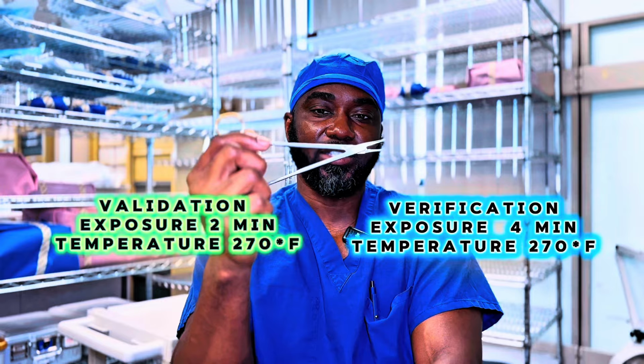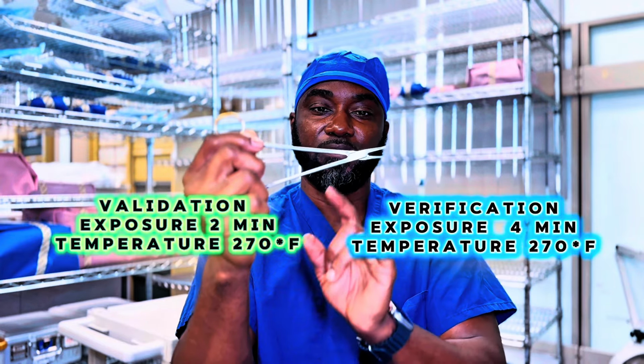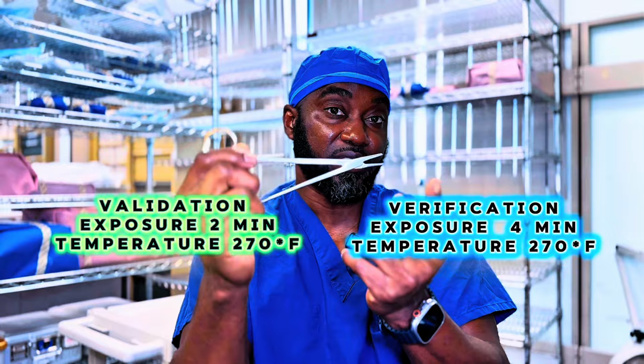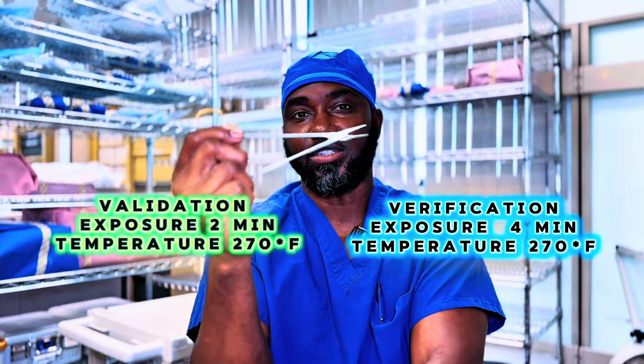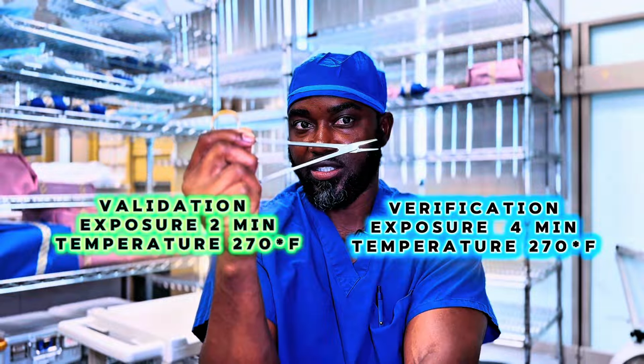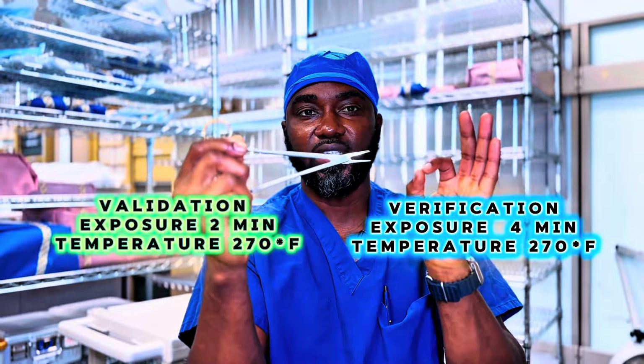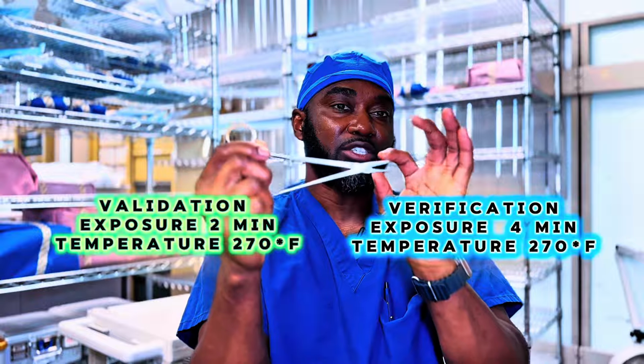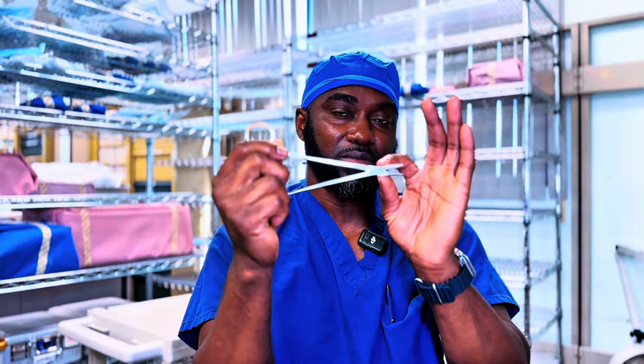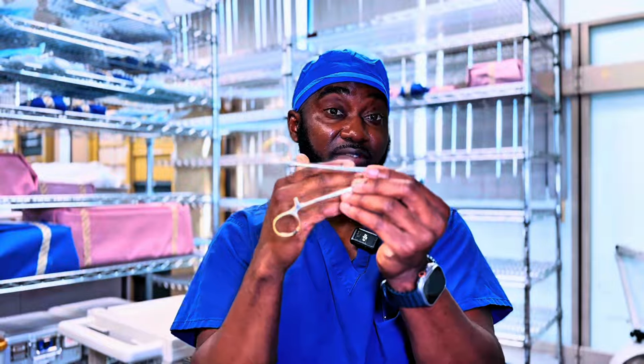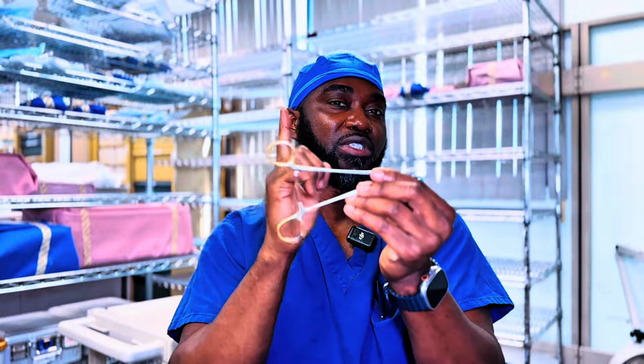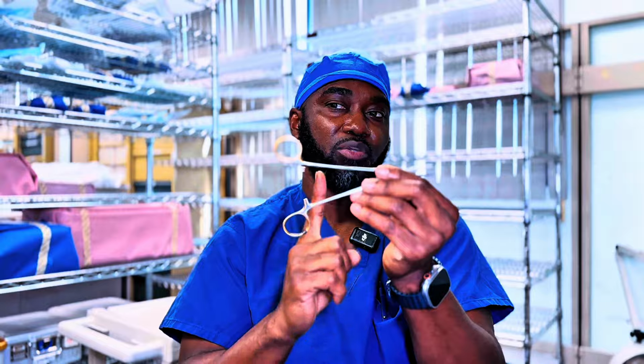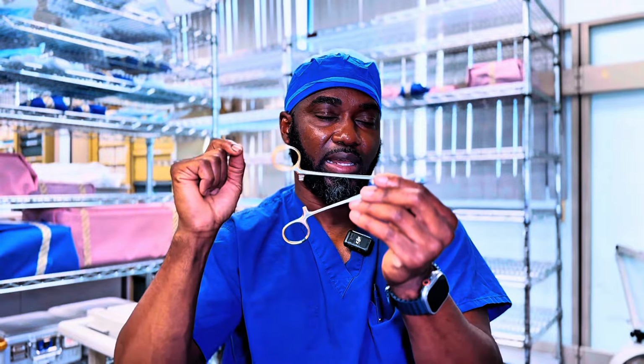What do I mean by half cycles? For example, if the manufacturer is trying to sterilize this instrument for 4 minutes at a temperature of 270 degrees Fahrenheit, the sterilization process will be 2 minutes, half the time, for 3 consecutive times, while the instrument is inoculated with microorganisms. It means that the instrument will be dirty for them to sterilize it, but they should sterilize it at half the time that will be recommended for use by the end user.